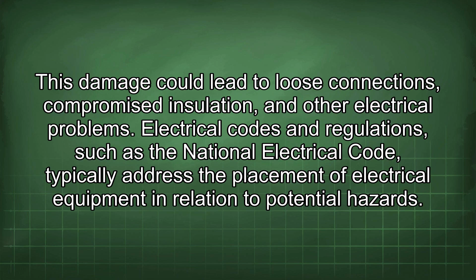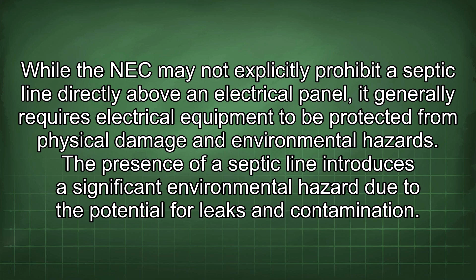Electrical codes and regulations, such as the National Electrical Code, typically address the placement of electrical equipment in relation to potential hazards. While the NEC may not explicitly prohibit a septic line directly above an electrical panel, it generally requires electrical equipment to be protected from physical damage and environmental hazards. The presence of a septic line introduces a significant environmental hazard due to the potential for leaks and contamination.